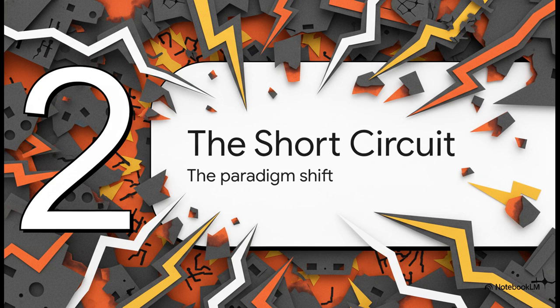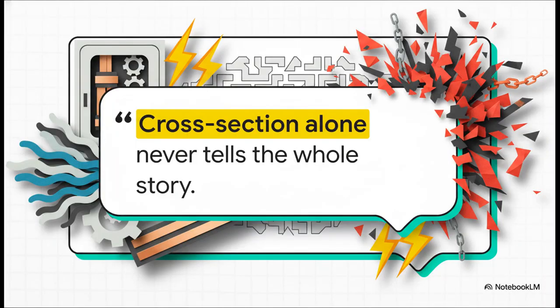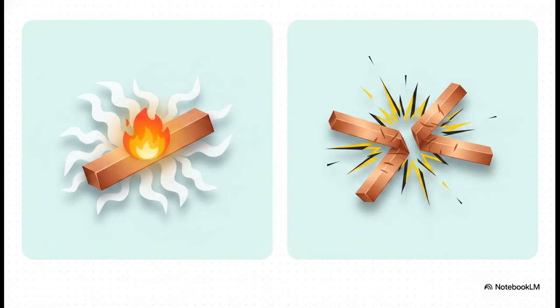Moving right along to Section 2, surviving the short circuit, the paradigm shift. Surviving a short circuit requires a complete paradigm shift from everyday continuous current to examining a highly destructive environment. Remember what we just discussed about sizing? Well, cross-section alone never tells the whole story. So the crucial point is this: a bus bar that effortlessly carries its continuous rated current without overheating can still fail catastrophically during a fault check. Short circuit performance demands we look at two entirely different types of destructive stress. A short circuit unleashes two highly destructive forces.